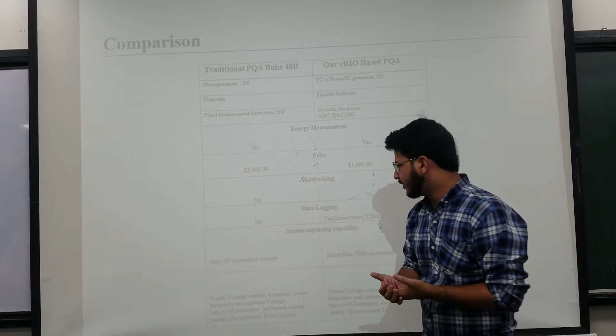So the price range is quite high for the traditional power quality analyzer. It is almost 36 or 37,000 dollars, and our cRIO-based power quality analyzer along with the PC costs only around $2,000. The traditional power quality analyzer does not have multitasking, it does not have data logging, and it can only create 20 screenshots of the results. It cannot store the results for a longer time, so it does not support data logging.